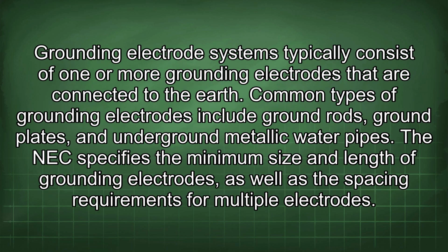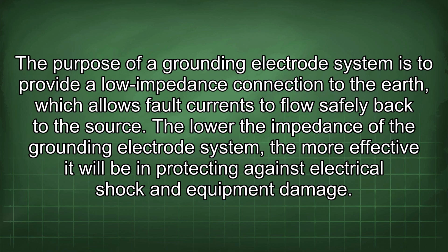Grounding electrode systems typically consist of one or more grounding electrodes that are connected to the earth. Common types of grounding electrodes include ground rods, ground plates, and underground metallic water pipes. The NEC specifies the minimum size and length of grounding electrodes, as well as the spacing requirements for multiple electrodes. The purpose of a grounding electrode system is to provide a low-impedance connection to the earth, which allows fault currents to flow safely back to the source.